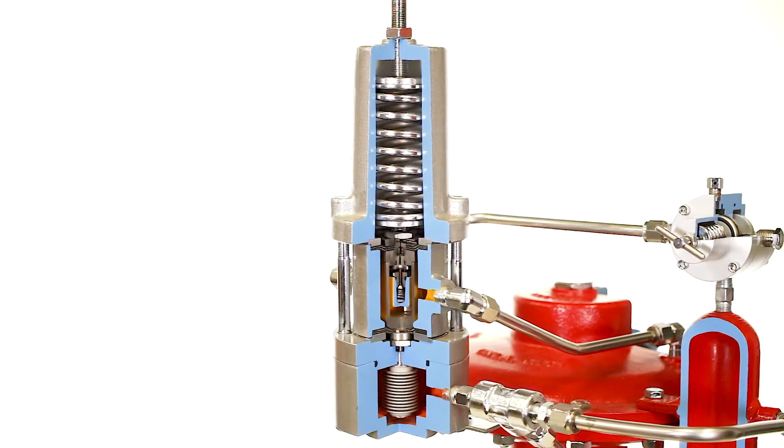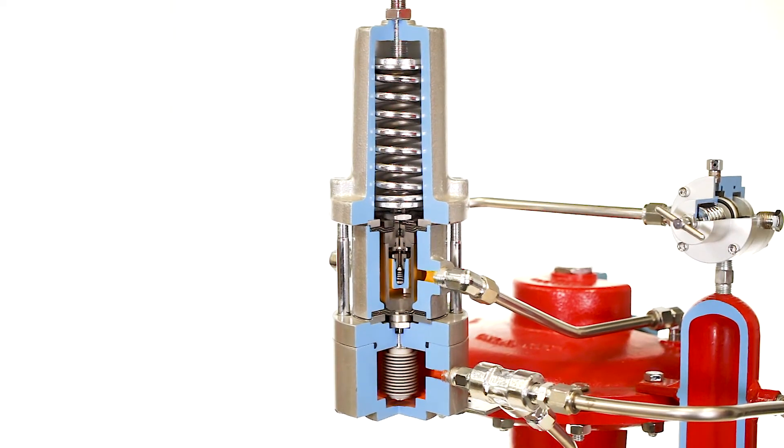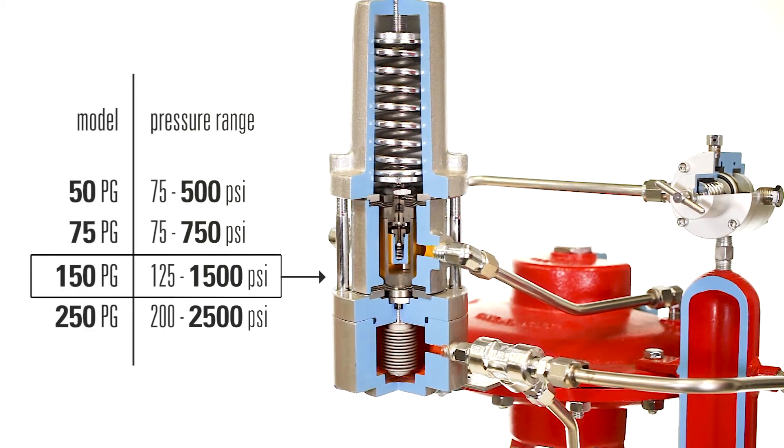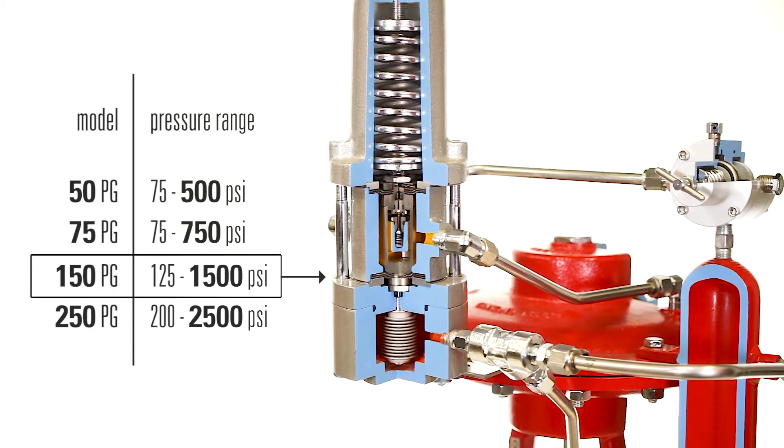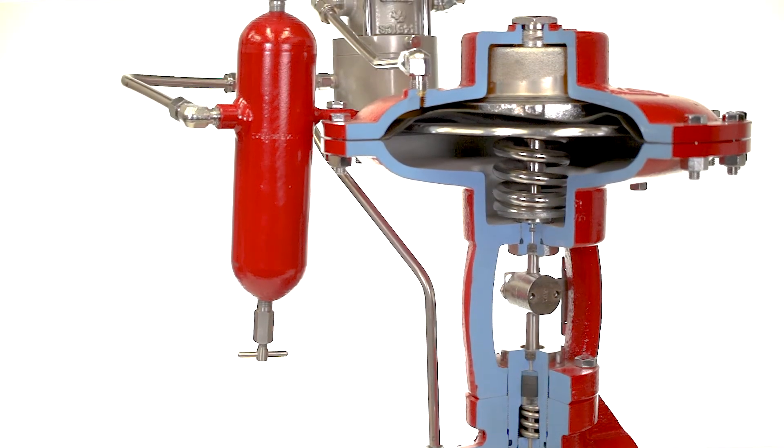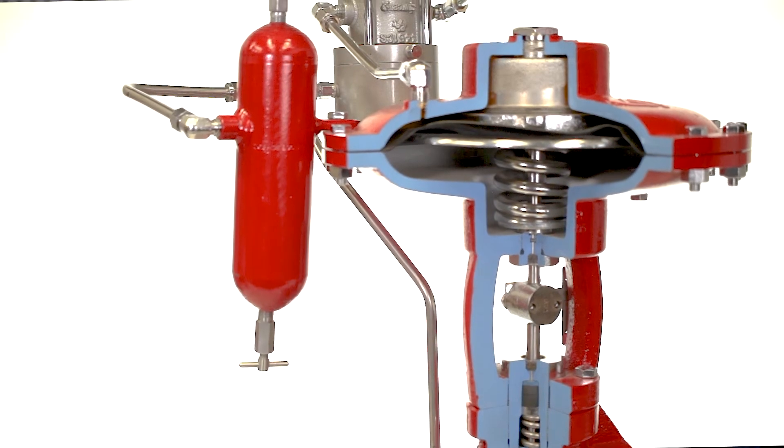Kimray's PG Pressure Pilot is used to monitor and control upstream or downstream pressure between 75 and 2500 psi, depending on the model. It does this by pneumatically positioning a control valve to achieve a desired set point. Here's how it works.